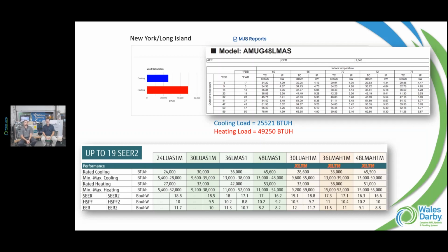But this is where we start, and I think you mentioned it, the balance point, understanding what we can get down to. Let's call it 14 degrees. I'm giving you 38,000 BTUs and I need an extra 10,000. That's where we get into the conversation of supplemental heat, whether it be electric strip, or maybe a current oil system or something like that, and it's very easy to install, as you're going to see in a few minutes.